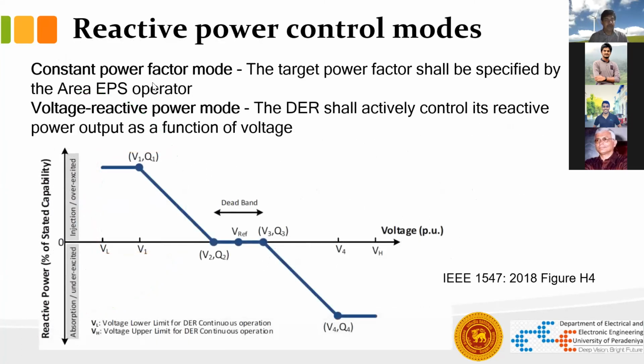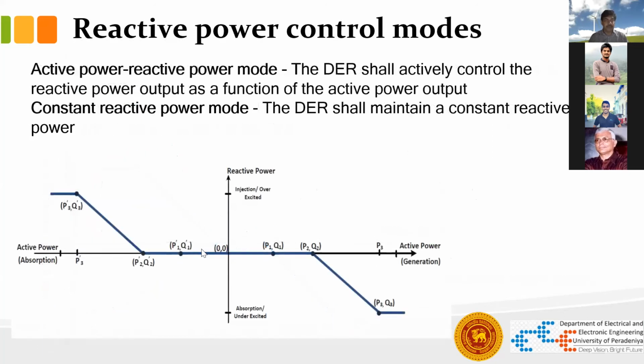So these are the 4 modes it's defined: the constant power factor mode, voltage reactive power mode, where the reactive power output is used. There's a dead band and 2 droops for controlling. Then the active power reactive power mode and the constant reactive power mode.